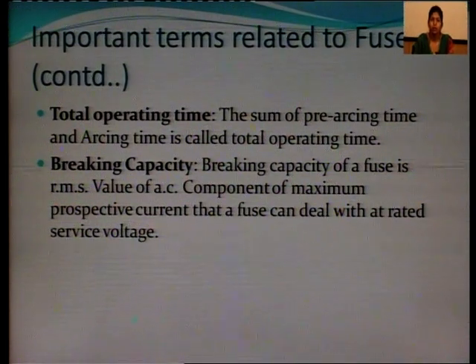The next is breaking capacity. Breaking capacity of a fuse is the RMS value of the AC component of the maximum prospective current that a fuse can deal with at rated service voltage. It is known as breaking capacity of the fuse.